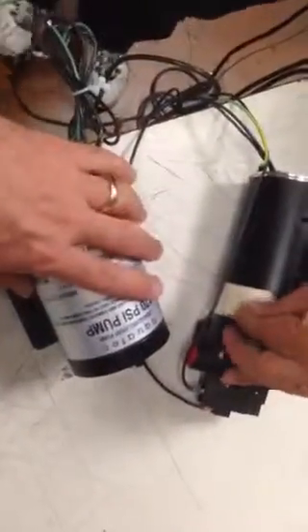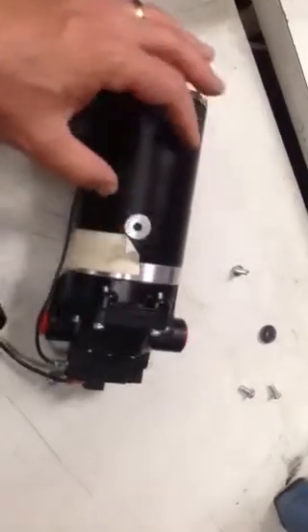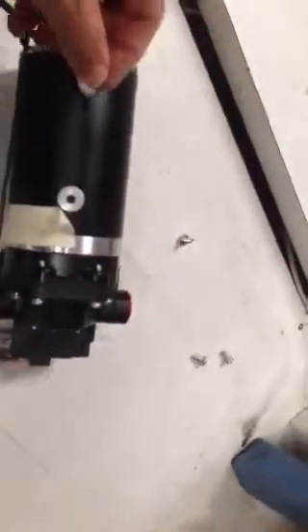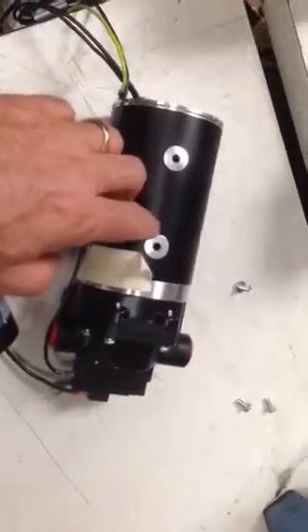So all you need to do is you've received some base plates, such as this one. Okay, so the first thing we're going to do with the base plate is you have two washers, such as these, with a gasket. These are intended to provide a seal for moisture intrusion. We're going to place our gasket washers like so on the motor. Just line up with the holes.